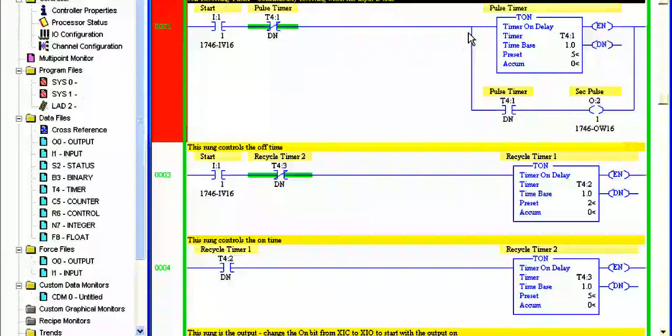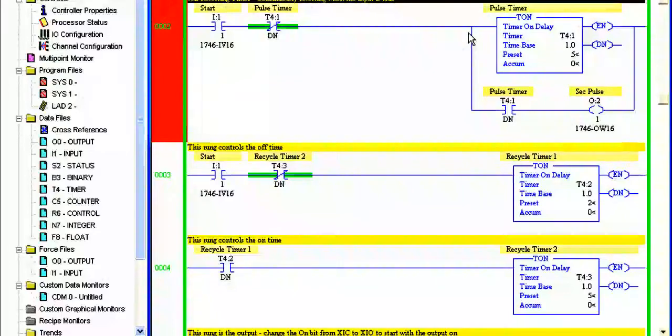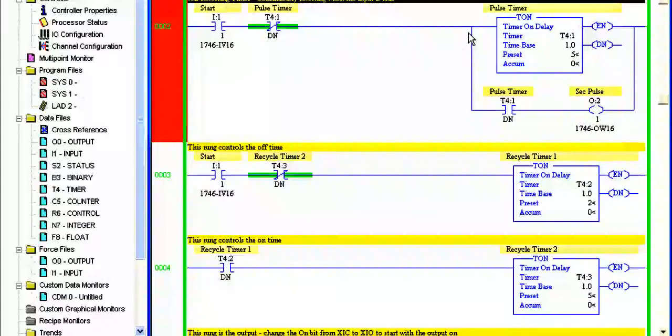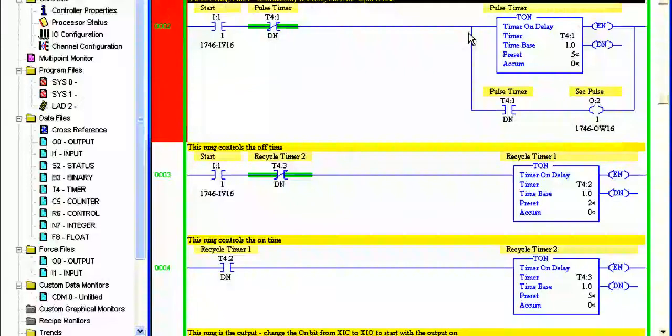On rung 2 we have a self resetting timer or a continuously resetting timer. Pretty common as an easy to build clock pulse. Just remember that the output's only going to be active for one scan when the time has finished its time period. So you can't really sensibly use that output to demonstrate something that's on because it's only true for one scan. But certainly for a time base, setting up a time base, a regular time base, it's pretty easy.